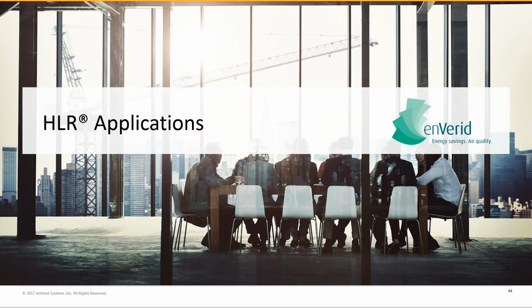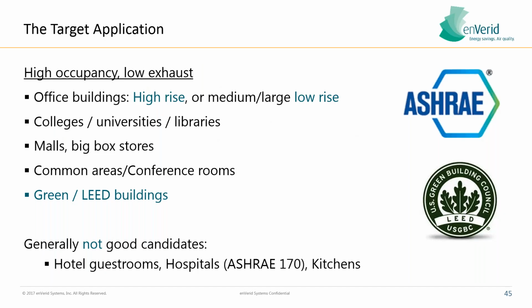In terms of applications, we've mentioned large office buildings. We've also mentioned colleges. Malls and big box stores are great applications, common areas and conference rooms, and obviously LEED buildings as well. Basically anywhere where you're looking to reduce outside air, and exhaust is not driving how much outside air is required. So in other words, occupancy should be the driving factor behind your outside air calculations, not exhaust.